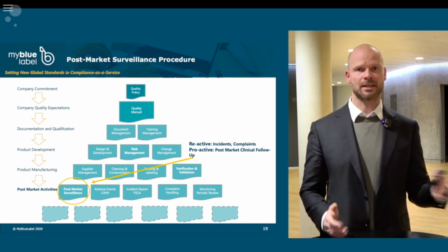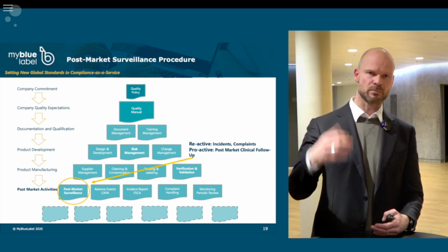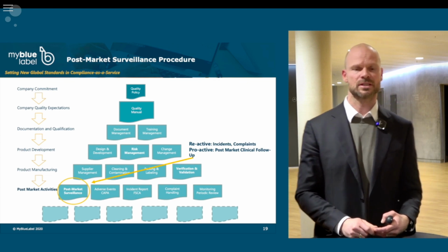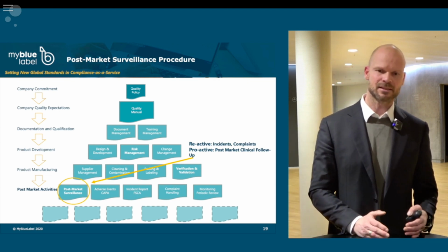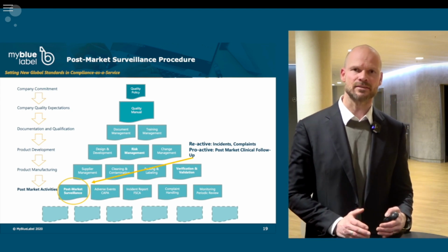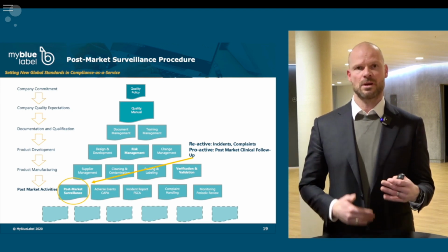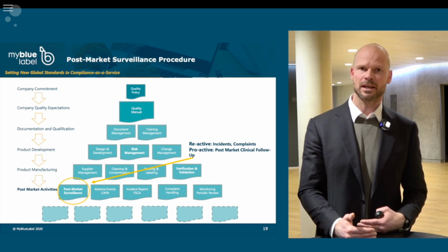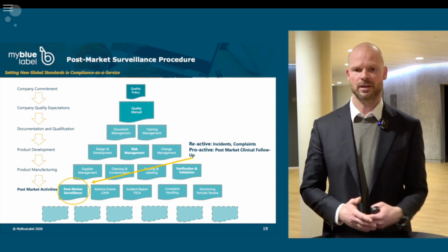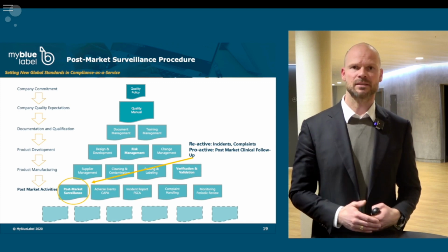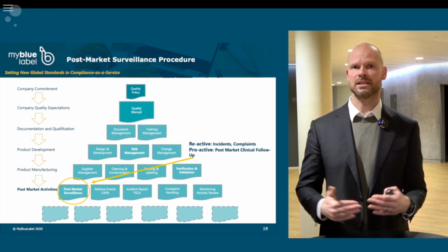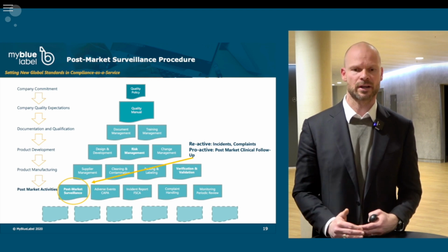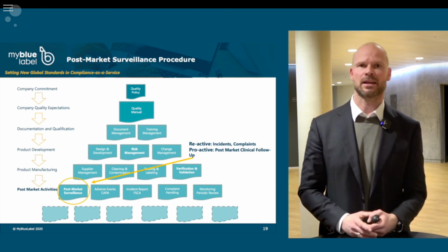You would not know that it is coming, but it comes from the patient using your system. So you need to collect incidents and complaints, and then you need to trend on those incidents and complaints. If it's a serious incident, then you need to report it. And if it's not a serious incident, then you need to trend on it and see if too many incidents are occurring. And that will feed directly back into your risk assessment.